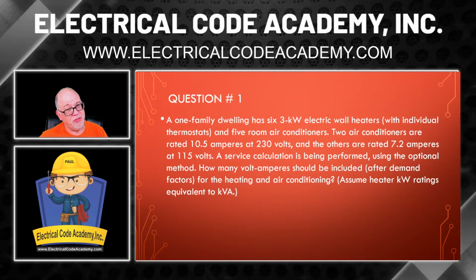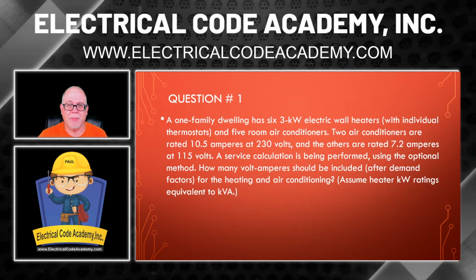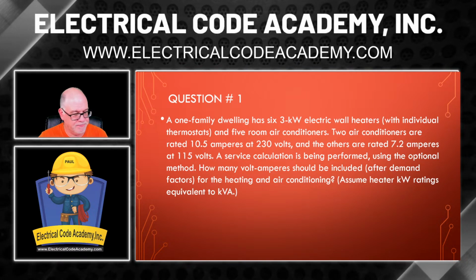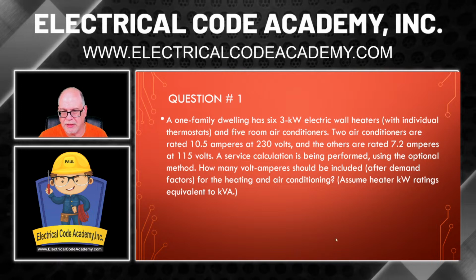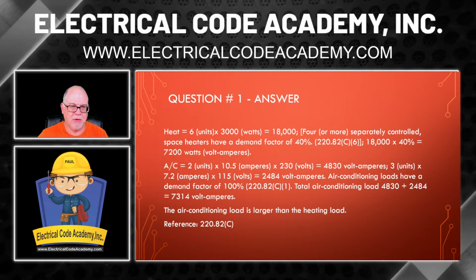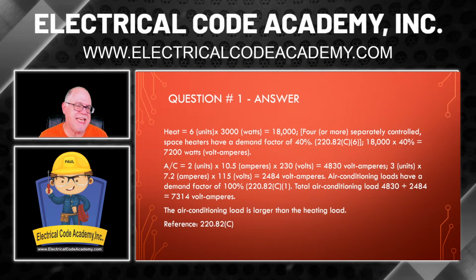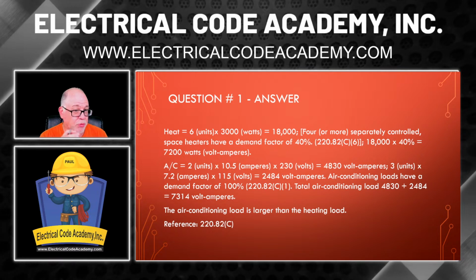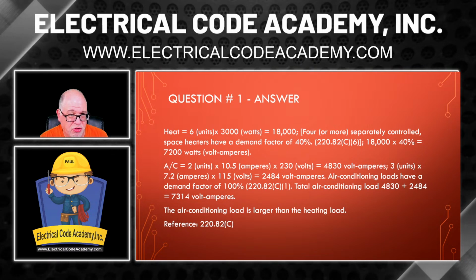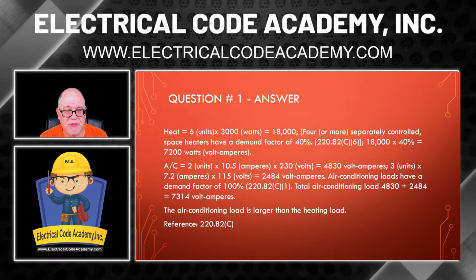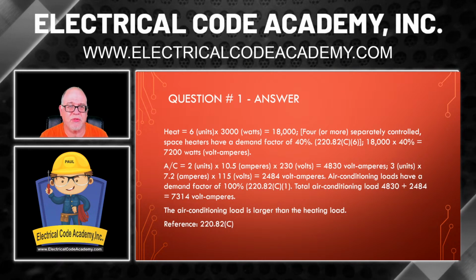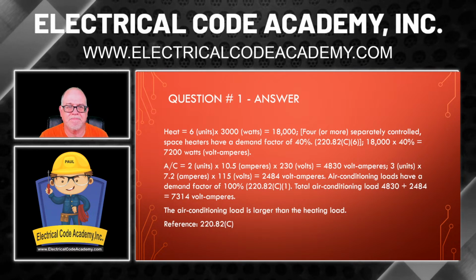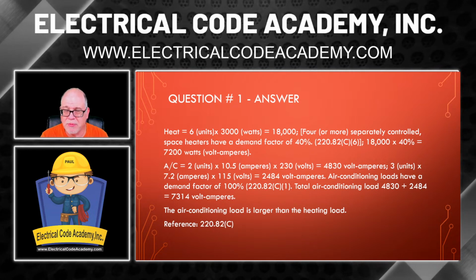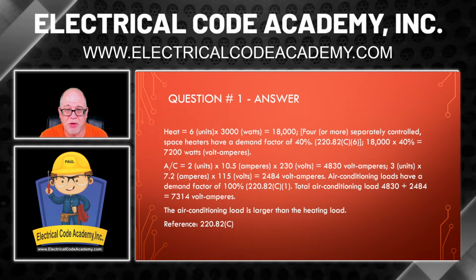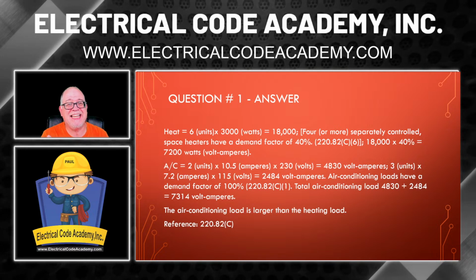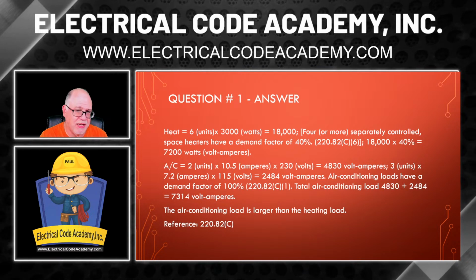So here was our question, and we got to do a couple things in order to get there. All right, so let's go on and start working the math. First thing, let's knock that heat out. There were 6 of them, 3,000 watts each, or 3 kW each. So we're going to work this out: 6 times 3,000, or 6 times 3 kW, equals 18 kW. But in this case, it's 18,000, the way we're working it out here.